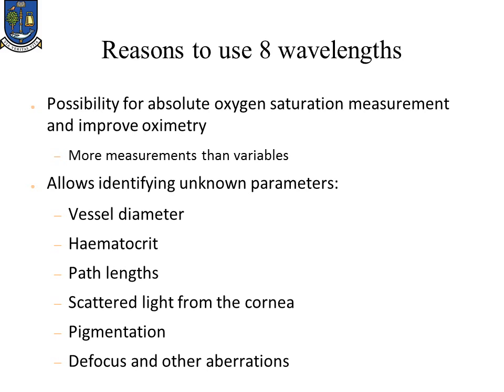So why do we use 8 wavelengths? Basically, because it gives the possibility to do absolute oximetry measurements and improve oximetry, especially the robustness of it. In this case, we will have more measurements than variables.